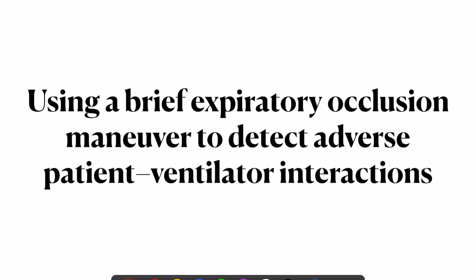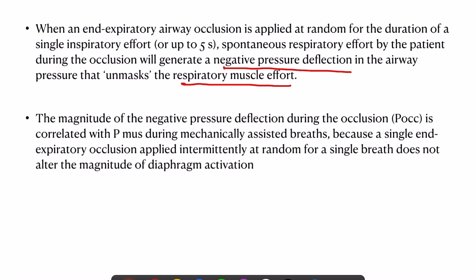So here, an end expiratory occlusion is applied at random for a duration of a single inspiratory effort or up to 5 seconds. The spontaneous respiratory effort by the patient during this occlusion will give a negative pressure deflection in the airway pressure that we are monitoring. This unmasks the effort of the respiratory muscle because you have blocked the effect of the ventilator. Now, the magnitude of the negative pressure deflection during this occlusion is the P-OCC, and it is correlated with the muscle pressure that is generated during assisted ventilation. And since it is a single end expiratory occlusion applied intermittently at random, it does not alter the magnitude of the diaphragm's activation.